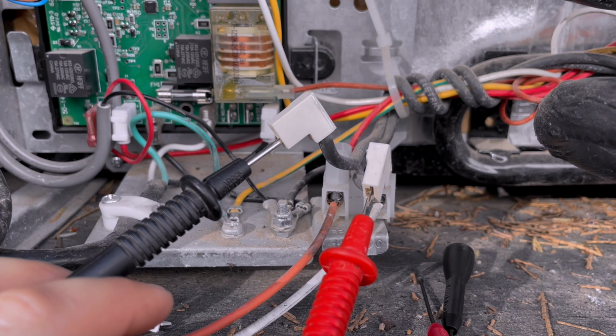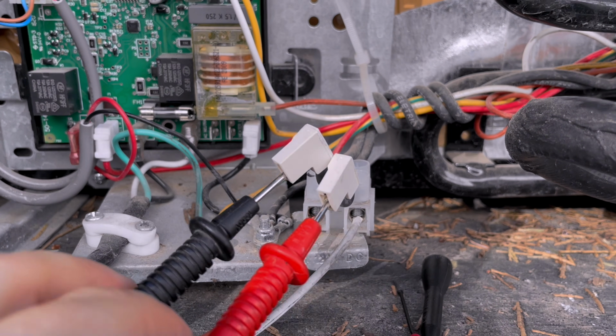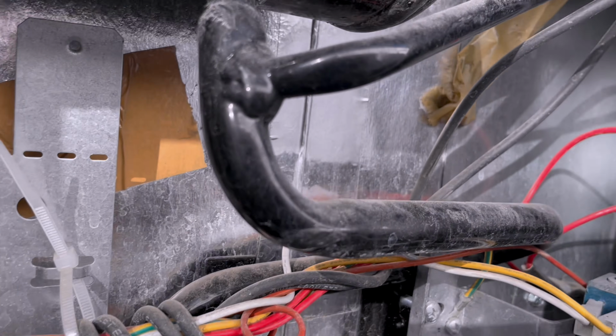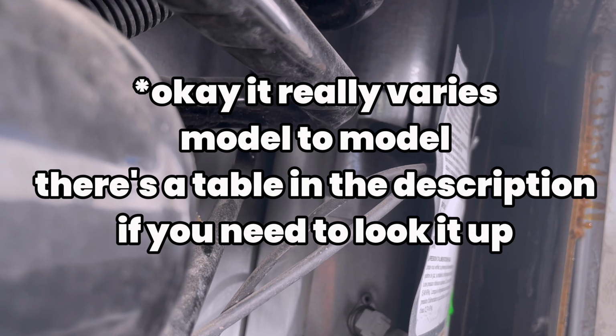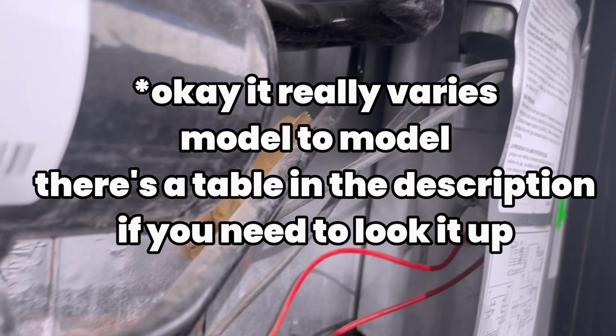If you're still getting 0 amps or close to 0 amps, and this tube is not getting hot, I would go ahead and disconnect them from the circuit board. Set your meter to resistance. Put one probe on either wire coming off of the heating element, and on a Dometic fridge you should be seeing a reading in the realm of this. If you are way off of that, then look at replacing that heating element.